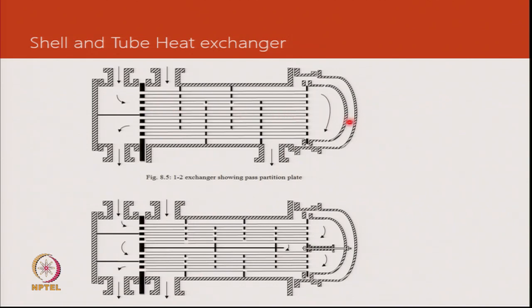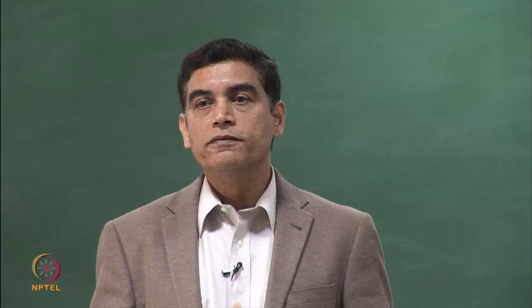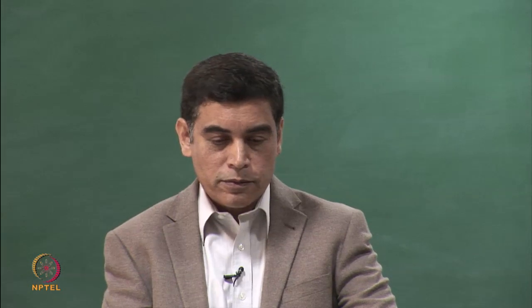Depending on the design, it could be a 2-pass or a 4-pass system, and the baffles determine how many times the fluid comes in contact with the tubes. The space between the tube sheets is enclosed, so the key requirement is that we must be able to seal the two fluids apart — we do not want water entering the refrigerant path or vice versa, as that risks performance.